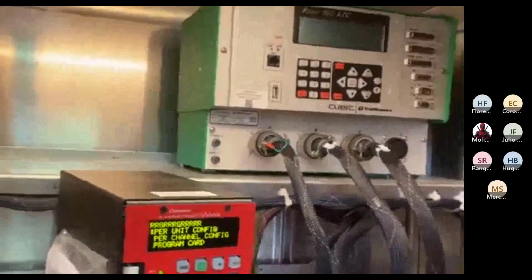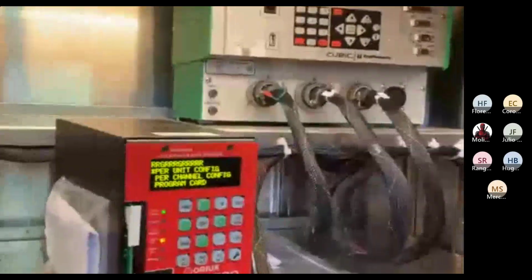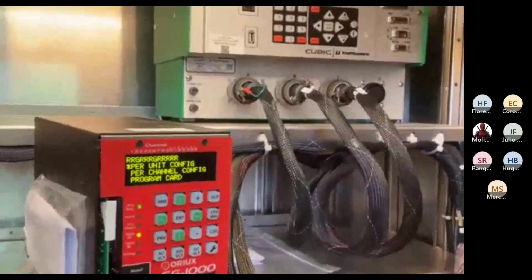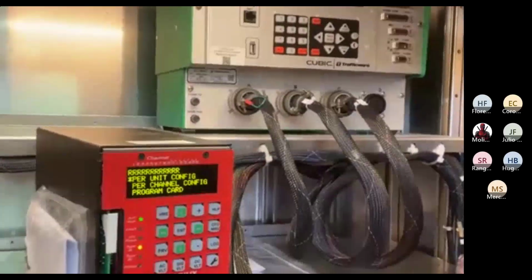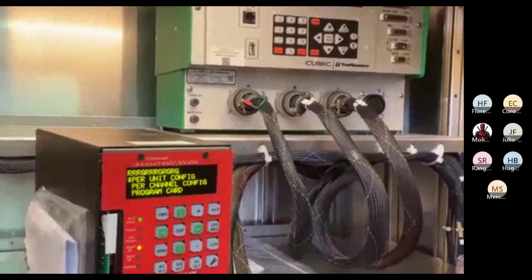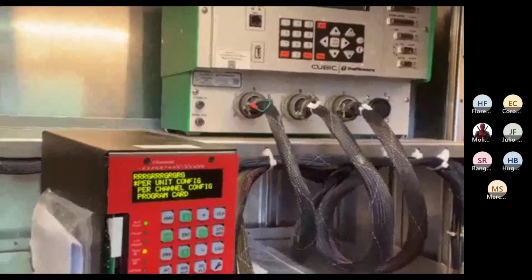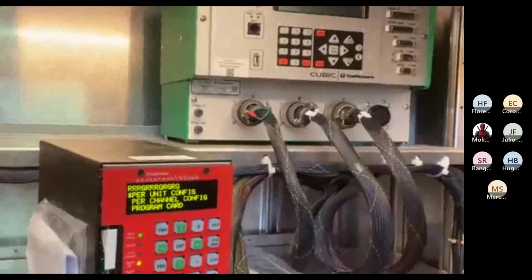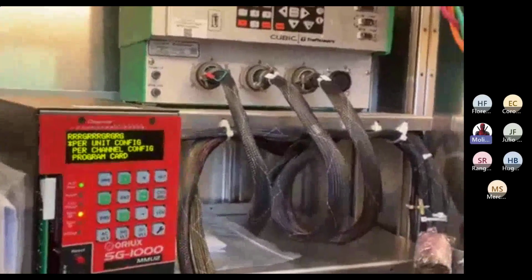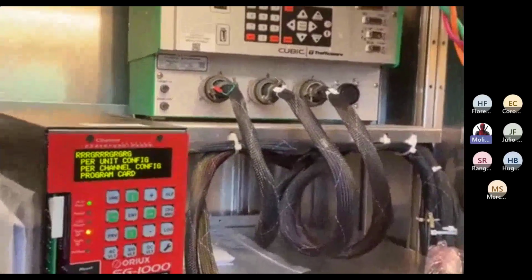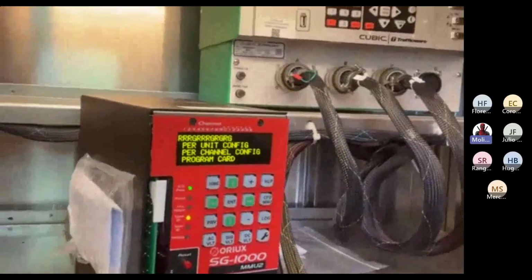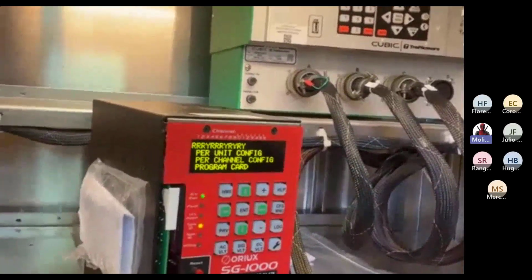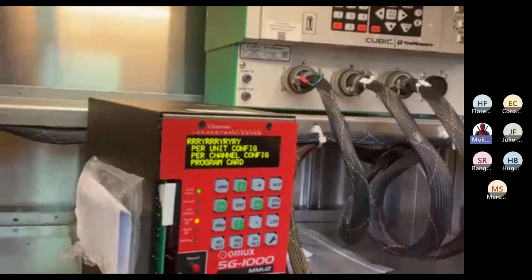But if you have a problem at a phase, you can always go back and look at the fault, because it's in the log. It'll log that event, whatever the fault was, with time and date. It's just the saved state of all the voltages that goes away. You also have that information in the log, but for the full log you have to download it and look at it on a computer to see all the information. Other than that, just the major events you can check, and if you just want to get it up and running, that's all you need.